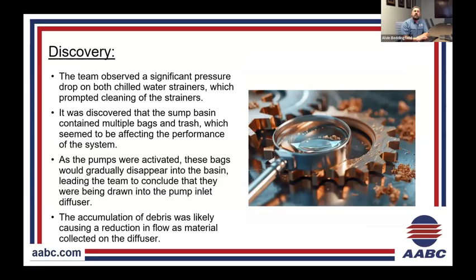So upon our discovery, the team observed pressure drop on both chilled water strainers. The strainers were excessive, so that was something we isolated, saying, okay, the strainers needed to be cleaned. I think they were at 8 PSI of drop across the strainers when we were actually proving design flow. So that was one thing we mentioned to the mechanical contractor: hey, the strainers need to be pulled and cleaned because they are excessive.